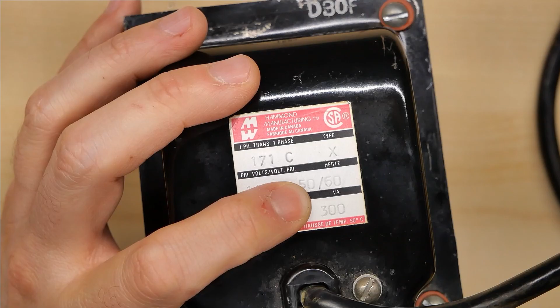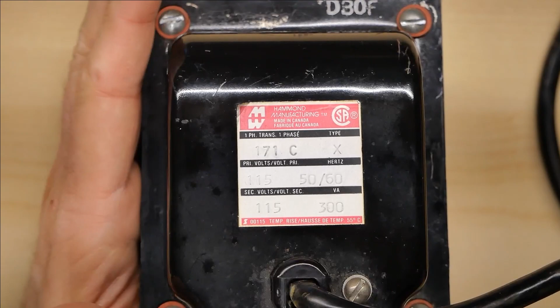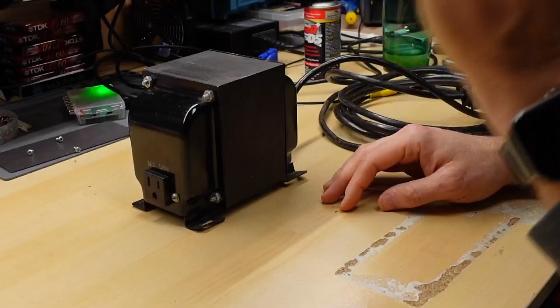Now right here you see it says 300 VA. VA stands for volts times amps, and that is a capacity rating of the transformer. Now you might be asking, what exactly is VA for a power rating compared to watts? Watts are pretty much what we work in when we look at electronics. You look at the label on something that says it uses 10 watts of power, for instance. Watts as a measure of power and VA as a measure of power sometimes can be the same thing.